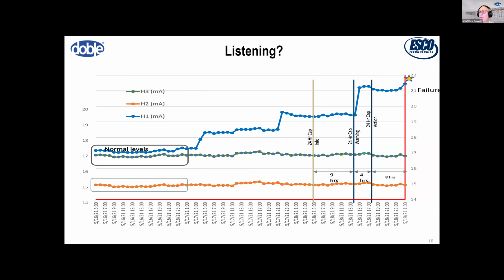Now the question is, what do you do when it reaches that level, and what about the next level? Another factor is how it rose in that exact moment, which affects how you interpret the test result - did it gradually rise, or was it a step change followed by steady readings? I can't tell you how many times someone has said, the bushing went up a little but then steadied out, it was okay - until it does it again, because it tends to get worse and worse until eventually the unit fails.